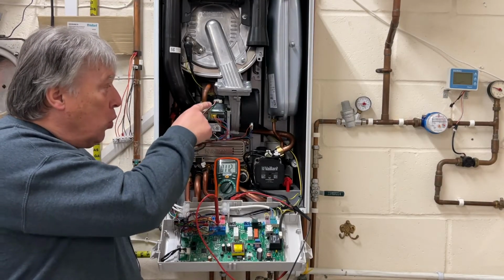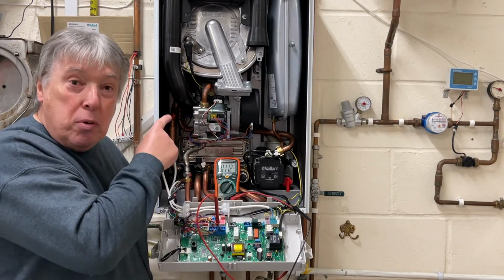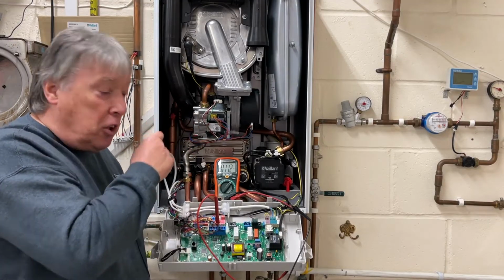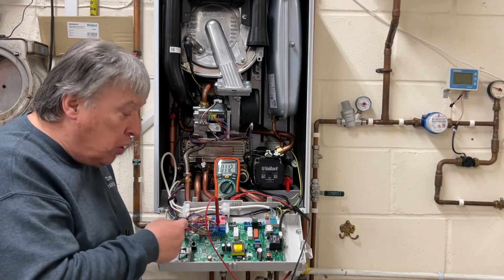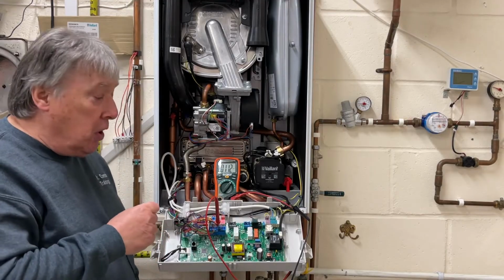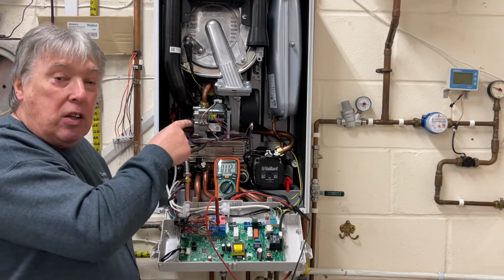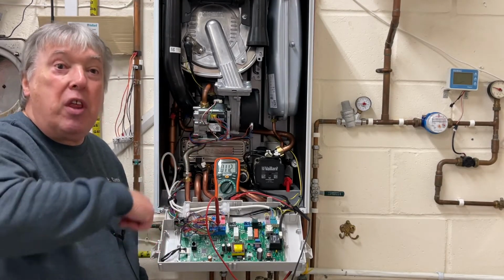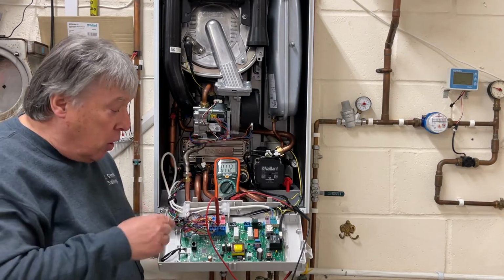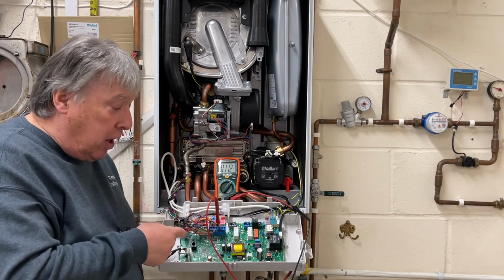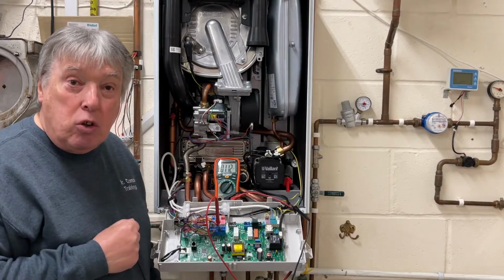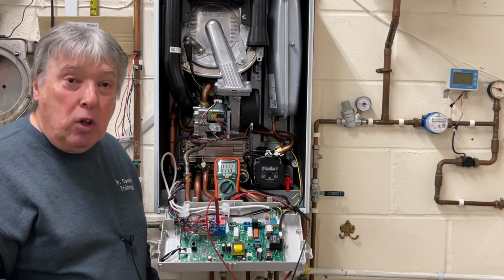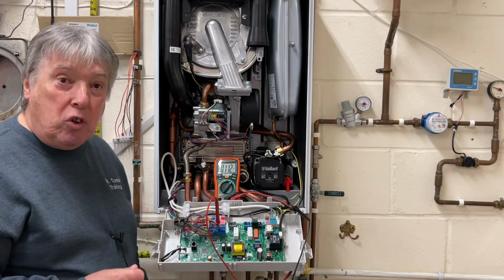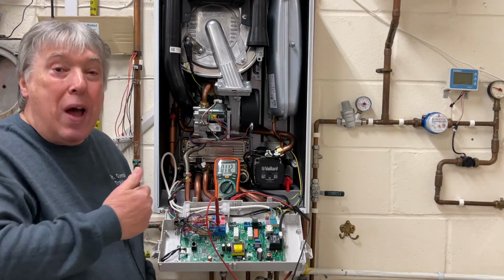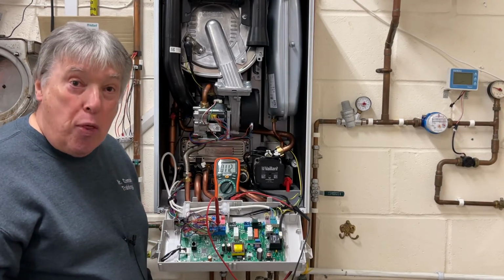So never make the connection up there, where you've got all these plugs - don't use the multimeter up there or unplug it. All our measurements are always done here, because if I just measure across the end, I don't actually measure the lead going in, through and out again. So all our measurements are done down here, and all I'm going to do is turn the tap on and look for my 2 volts, because it's 4 in and 2 out to earth.